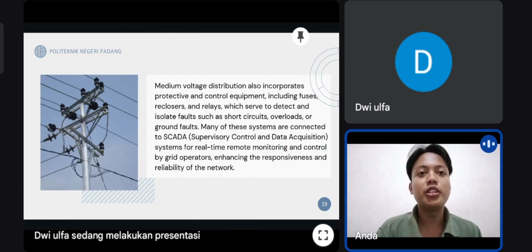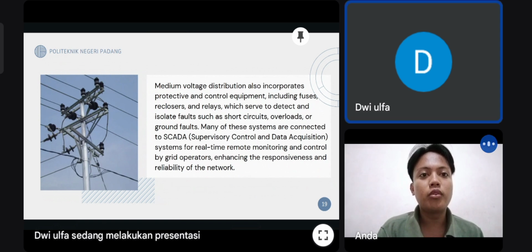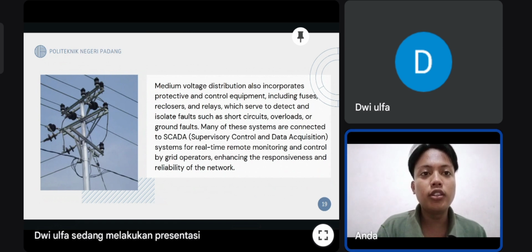Medium voltage distribution also incorporates protective and control equipment, including fuses, reclosers, and relays, which serve to detect and isolate faults such as short circuits, overloads, or ground faults. Many of these systems are connected to a SCADA system for real-time remote monitoring and control by grid operators, enhancing the supervision and reliability of the network.